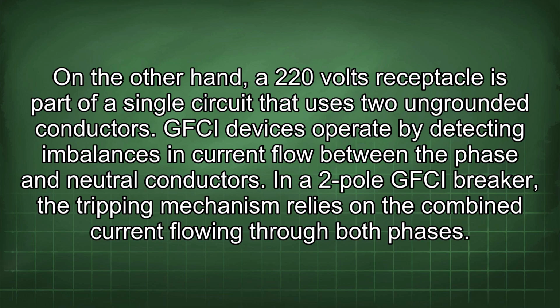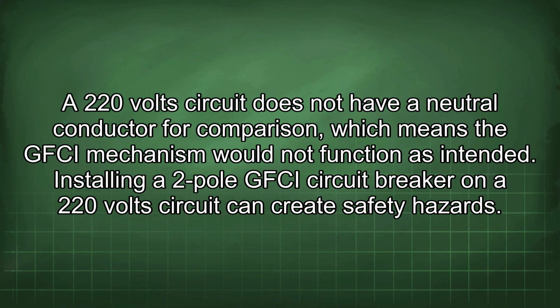GFCI devices operate by detecting imbalances in current flow between the phase and neutral conductors. In a 2-pole GFCI breaker, the tripping mechanism relies on the combined current flowing through both phases. A 220 volt circuit does not have a neutral conductor for comparison, which means the GFCI mechanism would not function as intended. Installing a 2-pole GFCI circuit breaker on a 220 volt circuit can create safety hazards.